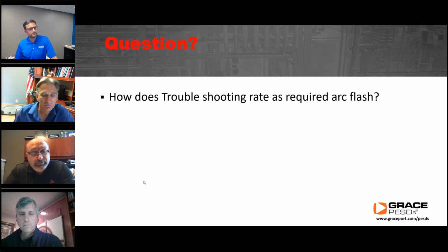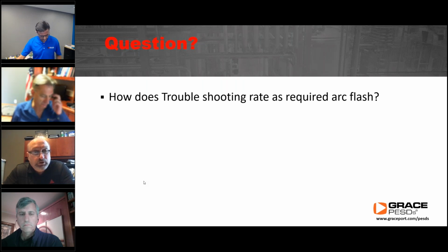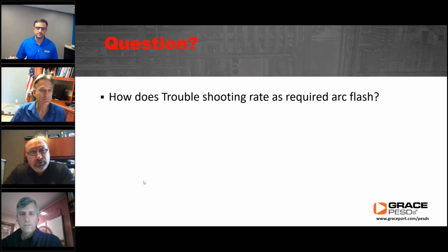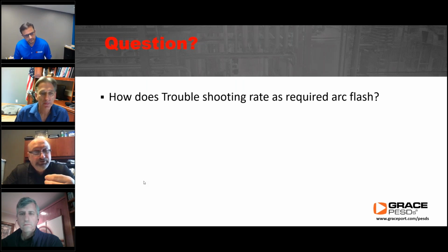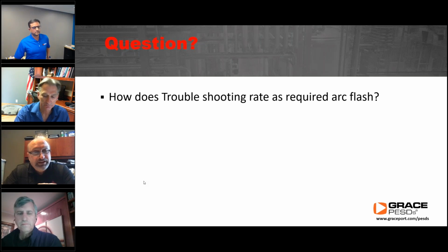If the work task is listed, then under condition of maintenance, the likelihood of occurrence of an arcing fault and arc flash is yes or no. So diagnostics and troubleshooting will require arc flash and shock PPE, but beyond that, you also have to look at the voltage of the electrical equipment and whether we can sustain an arcing fault and create an arc flash. So we have two starting points, and this is another change between Z462 and 70E: 30 volts is the starting threshold in Z462 for Canada, and it's 50 volts for NFPA 70E. So then you have to look at the work task, then at the maximum voltage of exposure, and whether an arcing fault and arc flash can be sustained above those low-end thresholds, and then decide if you need arc flash PPE, by doing an arc flash risk assessment.